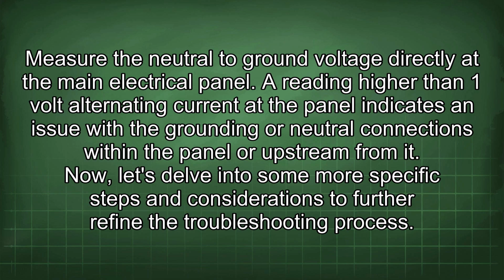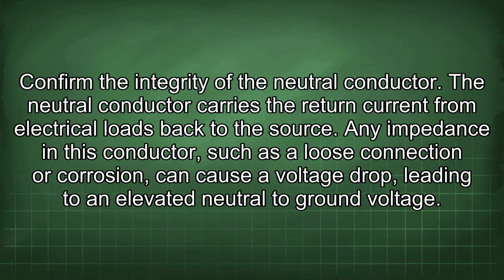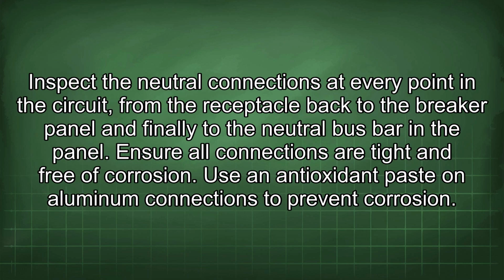Now, let's delve into some more specific steps and considerations to further refine the troubleshooting process. Confirm the integrity of the neutral conductor. The neutral conductor carries the return current from electrical loads back to the source. Any impedance in this conductor, such as a loose connection or corrosion, can cause a voltage drop, leading to an elevated neutral to ground voltage. Inspect the neutral connections at every point in the circuit, from the receptacle back to the breaker panel and finally to the neutral bus bar in the panel.